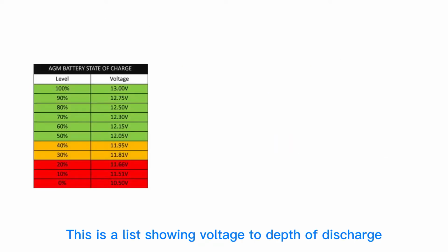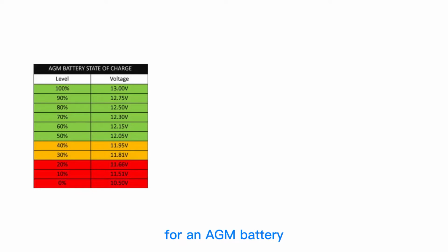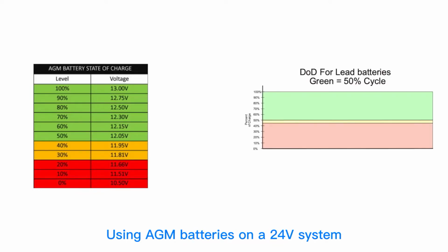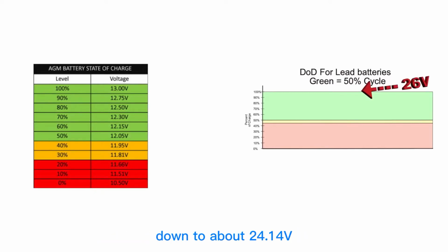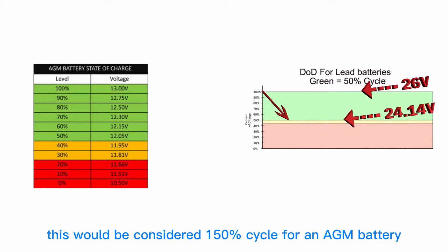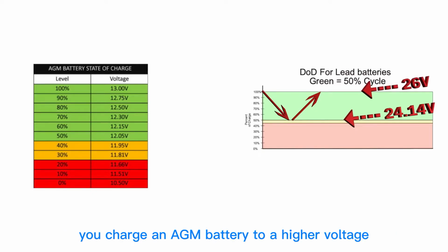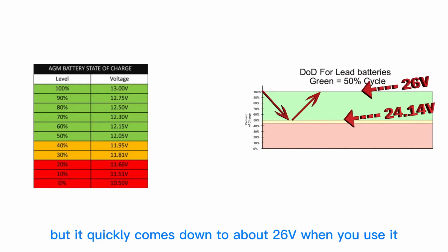This is a list showing voltage to depth of discharge for an AGM battery. Using AGM batteries on a 24-volt system, you will cycle the voltage from about 26 volts down to about 24.14 volts. This would be considered one 50% cycle for an AGM battery. You charge an AGM battery to a higher voltage, but it quickly comes down to about 26 volts when you use it.